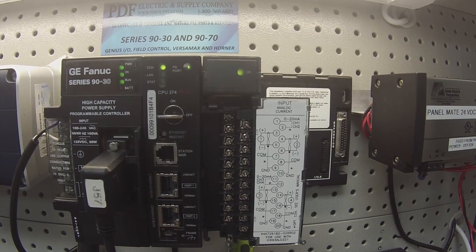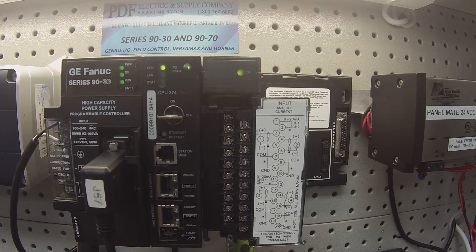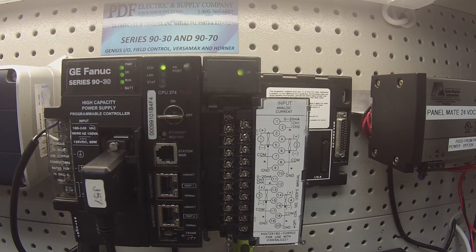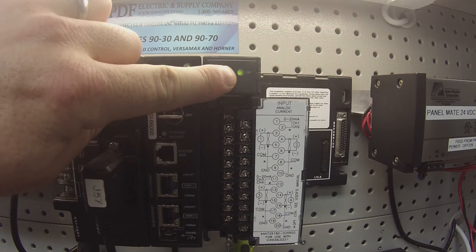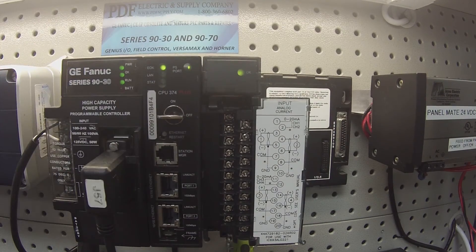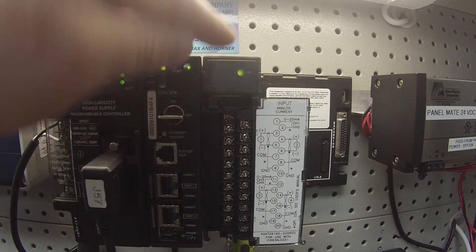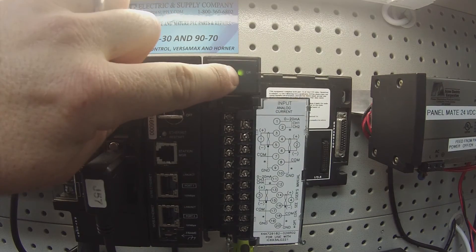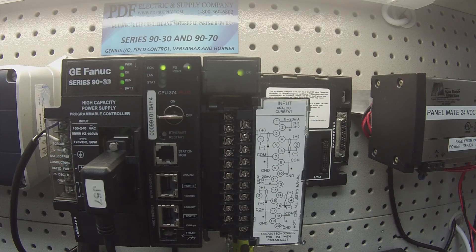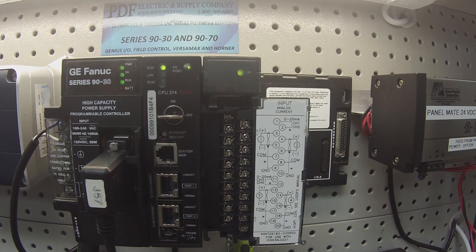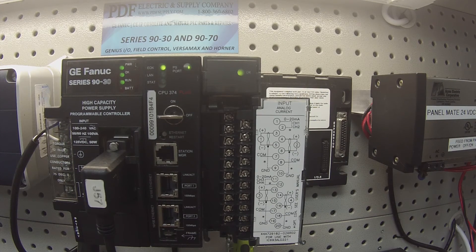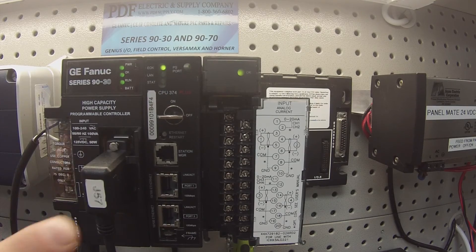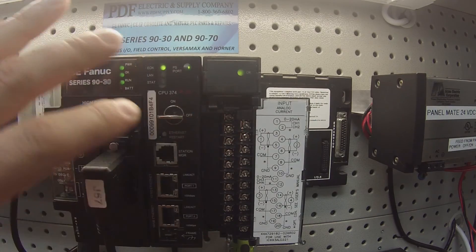So those are the things that I look for. Number one, if you think there's a problem with the analog card, the first thing you want to check is that the okay light is on. There are some instances where the light has been bent and it's not showing through the window. That's usually not the case, but it has happened. So first check to see if the okay light is on, then check to see that all the channels are giving you the exact same reading.